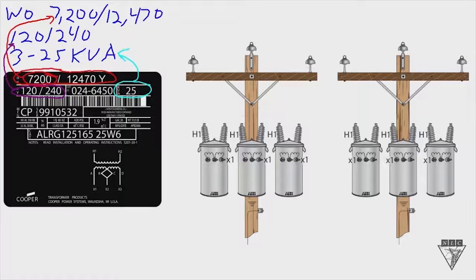So when we're banking transformers together, there's 2 other things that we need to look at. And the first one I'm going to circle and we're going to talk about is the impedance. So when you think of impedance, think of resistance. And you want to try and get 3 transformers that have the impedance as close to each other as possible. So we've got 1.9% as our impedance.